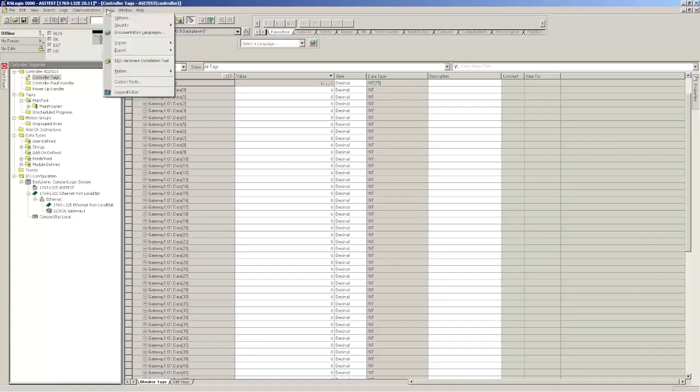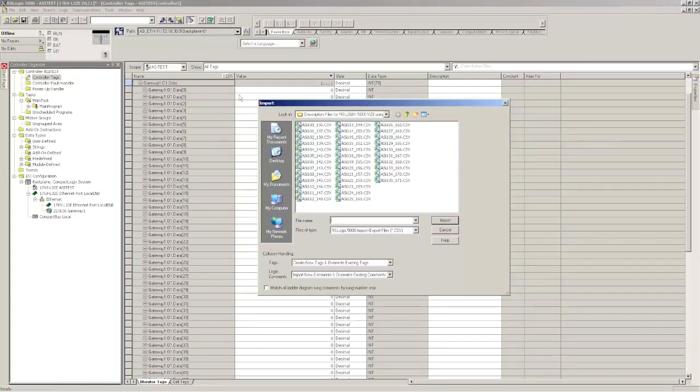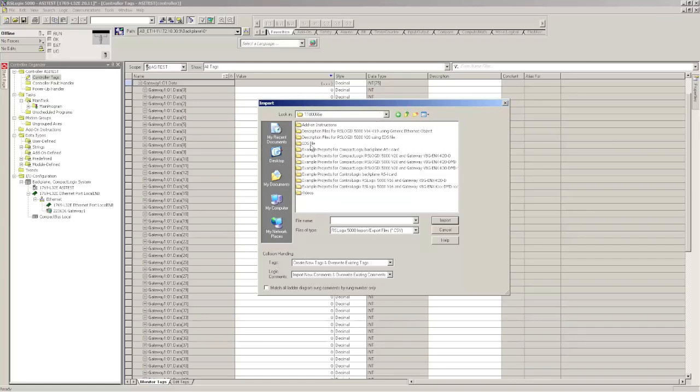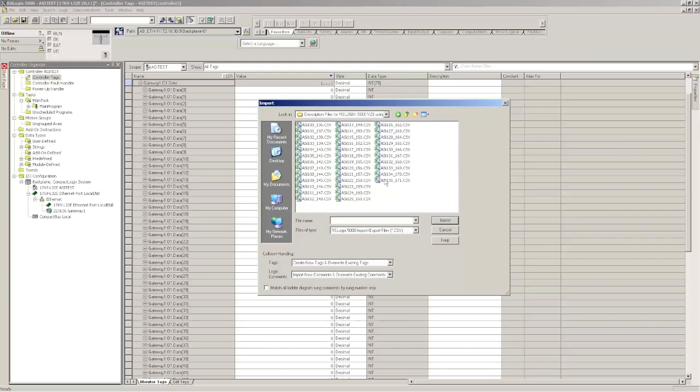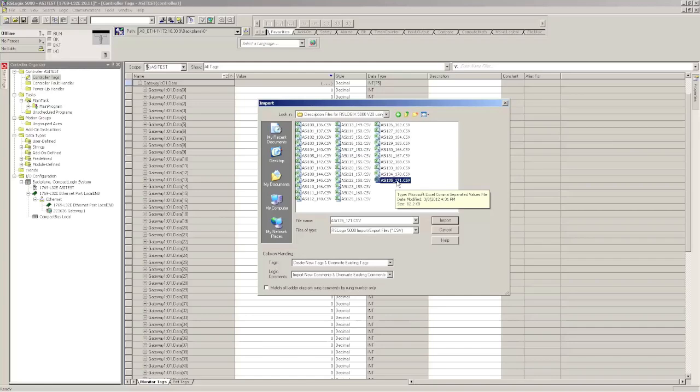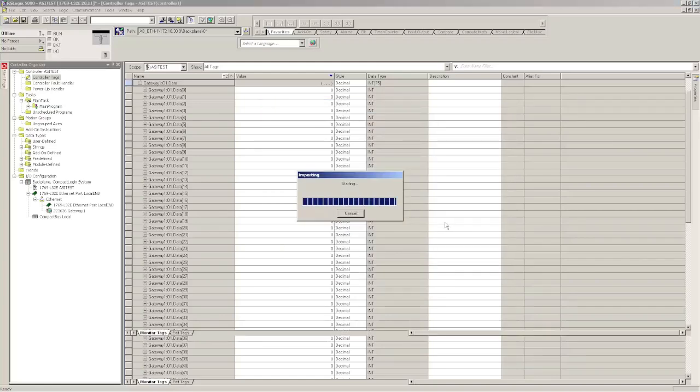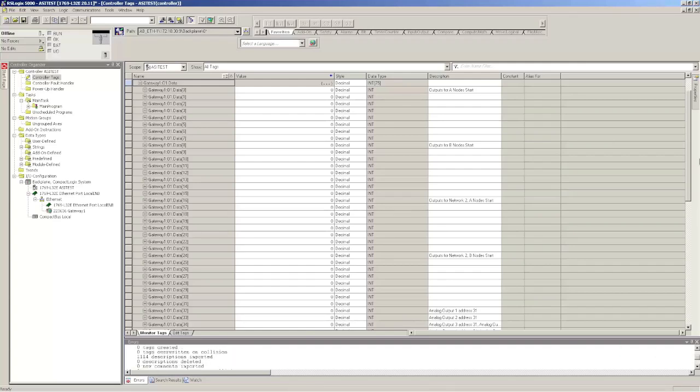What I did was I did this for you already. If you go to Tools, Import, Tags and Logic, go to the project I had you download. It's under the O66. Go to Description Files for RSLogix 5000 version 20 using CSV file. Remember I said, remember 135.171—that's the file name of this description file. Choose Import. No errors, no warnings. It imported over 1100 descriptions.